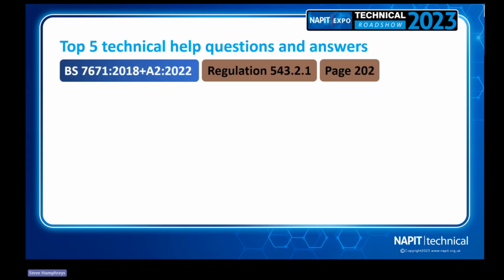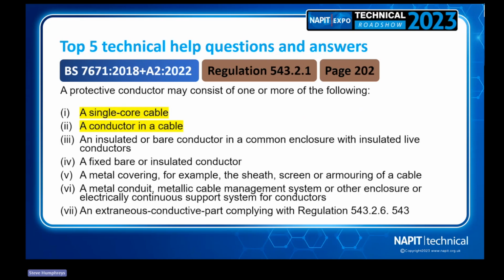The second part of that question, really on 543.2.1, is: if we know we need one, what do we actually need to use? Assuming it's a domestic situation, we haven't got metallic containment or conduit or trunking that can be used as the CPC, so we're really looking at indents 1 and 2. Practically this would involve either a rewire in twin and earth, where the conductor would be in the cable, or another option is to run a single core cable of the appropriate cross-sectional area to each of those lighting points that require that CPC to be there.